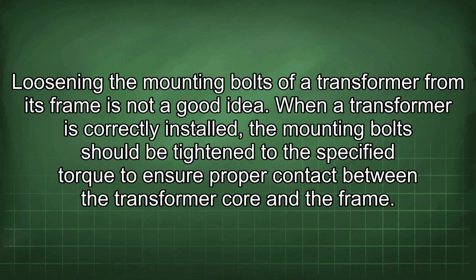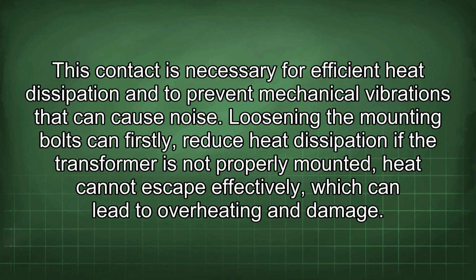Loosening the mounting bolts of a transformer from its frame is not a good idea. When a transformer is correctly installed, the mounting bolts should be tightened to the specified torque to ensure proper contact between the transformer core and the frame. This contact is necessary for efficient heat dissipation and to prevent mechanical vibrations that can cause noise.